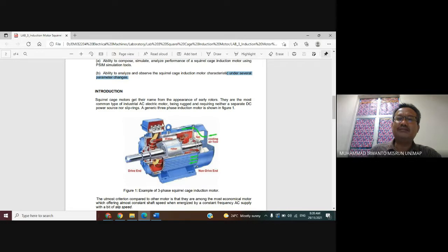Here is the supply terminal, because it is RST, three phase, for example RST or UVW. Here we give the symbols U1, V1, W1, and U2, V2, W2. And then how to connect the terminals depends on how we want to start it, using delta or Y connection.